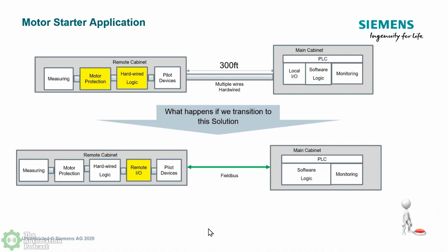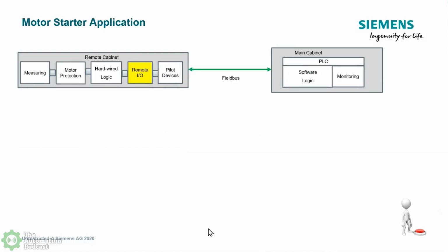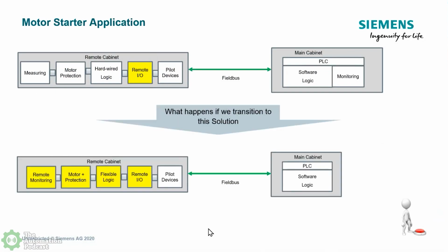So anyway, moving along. With that stated, introducing the field bus, you kind of see a trend where things are moving out, where you're getting remote control, flexible logic, not just hardware logic, and then remote I/O and pilot devices, of course, and then motor protection, which nowadays the majority has switched to a solid state overload or some type of motor protection and removed some of the old bimetallic heaters, or solder pots, as some guys have called them, that have been around a long time.